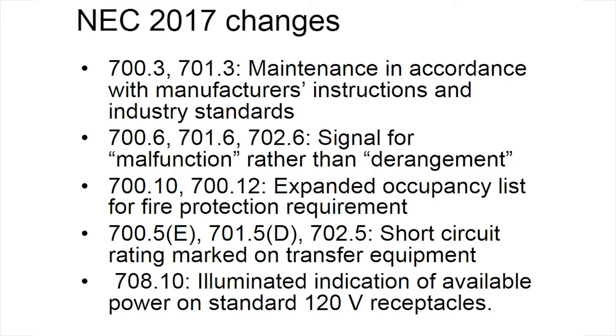700.10 and 700.12 expanded the occupancy list for the fire protection requirement and added hospitals and certain educational facilities. 700.10 calls for protecting feeders. 700.12 calls for protecting the room in which the emergency source, the generators, are. There's also a requirement that short circuit ratings be marked on the enclosure of transfer equipment, new to this code.